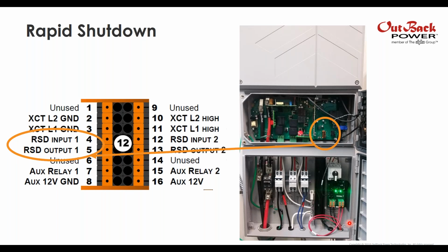If you'd like to connect rapid shutdown, it's easy enough to do there in the terminal block. Again, this is our power metering board, and that terminal block is located right there. So you'd connect 4 and 5 into your rapid shutdown, and then if you were doing stacking, you would also connect your outputs to the next system in the stack.